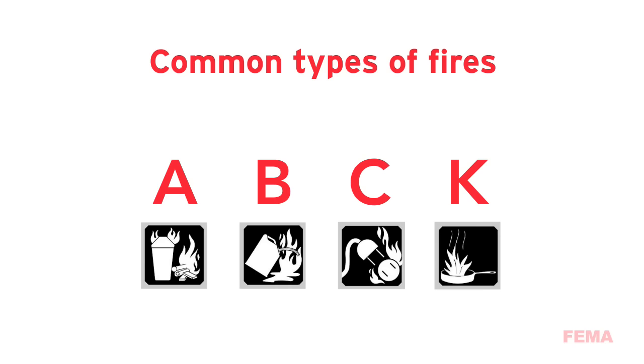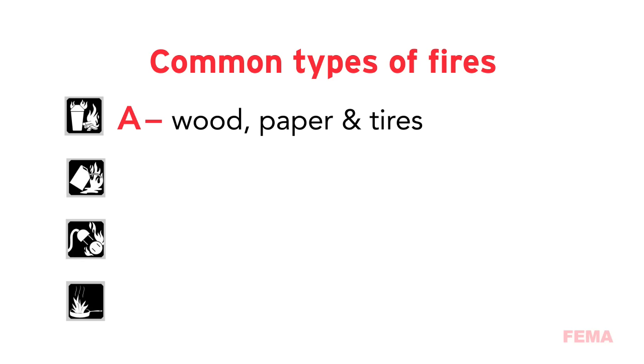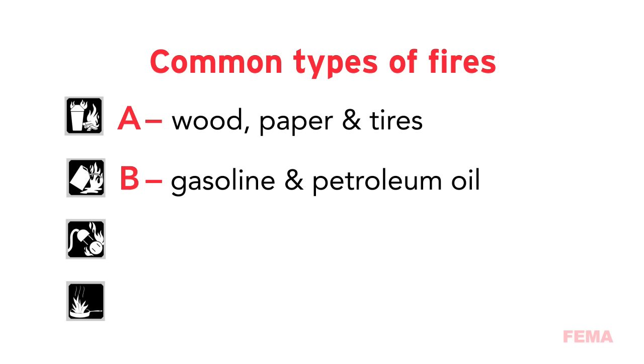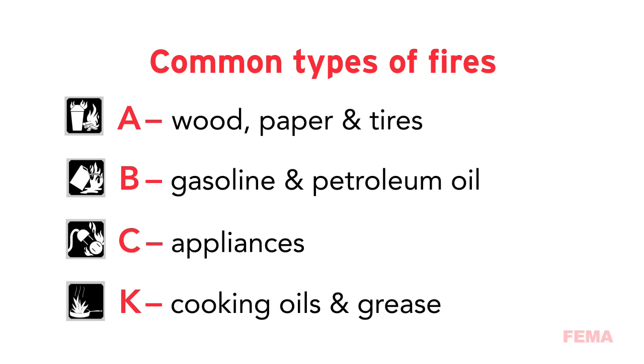Most common classes of fires are A, B, C, and K. Class A fires involve common combustibles like wood, paper, and tires. Class B fires involve flammable liquids like gasoline and petroleum oil. Class C ratings involve energized equipment for things that are plugged in, like appliances, computers, televisions, and electric machinery. Class K fires involve cooking oils and greases like vegetable fats.